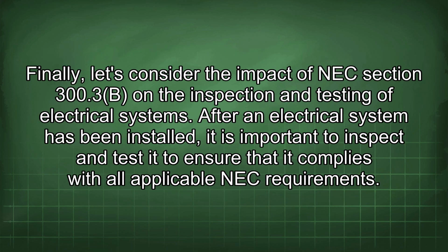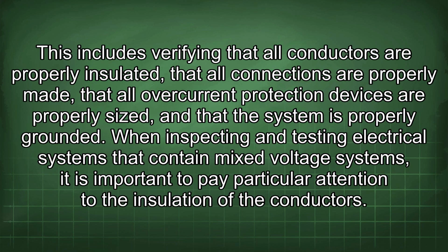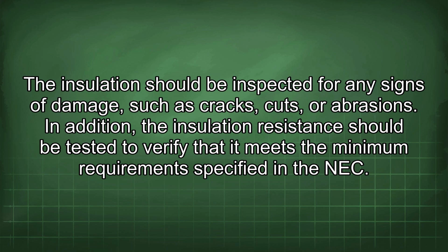are met. Finally, let's consider the impact of NEC Section 300.3b on the inspection and testing of electrical systems. After an electrical system has been installed, it is important to inspect and test it to ensure that it complies with all applicable NEC requirements. This includes verifying that all conductors are properly insulated, that all connections are properly made, that all overcurrent protection devices are properly sized, and that the system is properly grounded. When inspecting and testing electrical systems that contain mixed voltage systems, it is important to pay particular attention to the insulation of the conductors. The insulation should be inspected for any signs of damage, such as cracks, cuts, or abrasions.